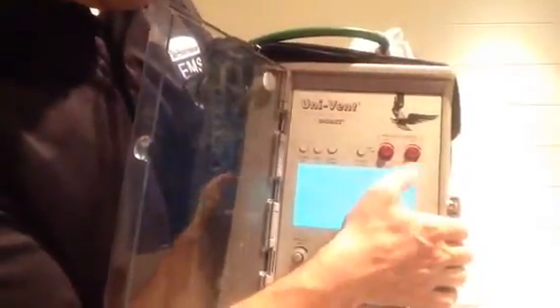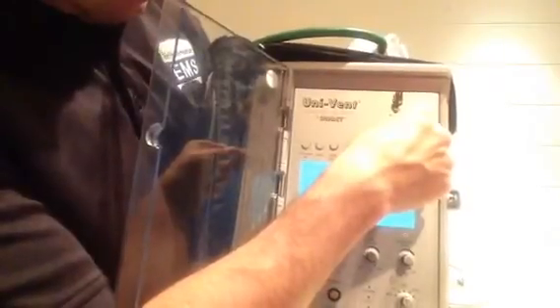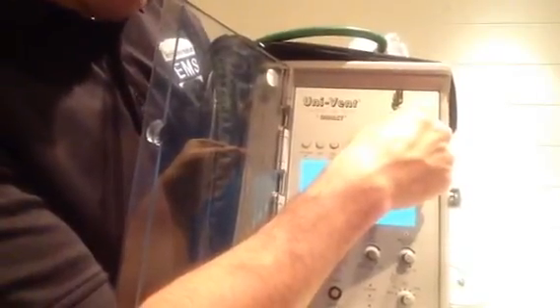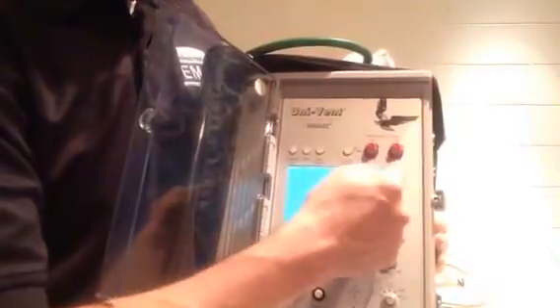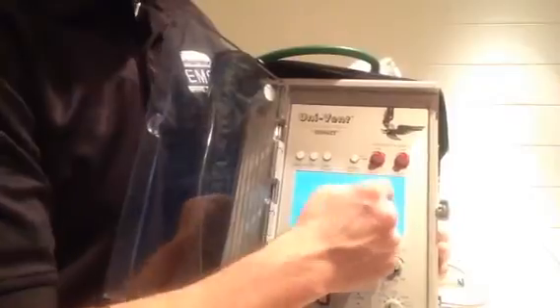Finally, we have our high pressure setting, and right now it's currently set at 46. We can go ahead and drop that down. And at the moment, we're going to go ahead and drop it down to 35. And then, of course, our low pressure alarm, we never want it set on 0. So right now, it's set on 8, and that's a nice safe setting. So if there was a vent disconnect or some other issue, you would immediately start getting alarmed because you have pressure lower than 8. The last aspect is going to be your PEEP.